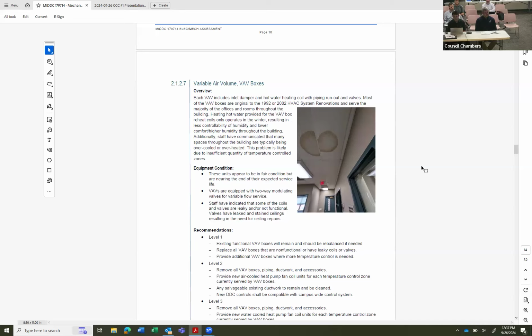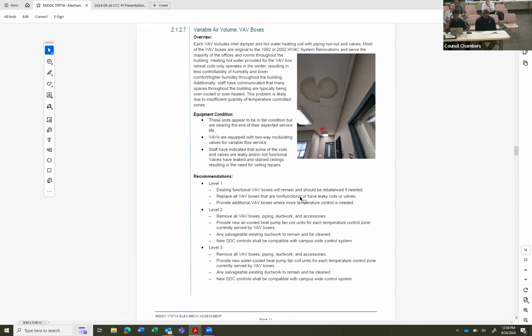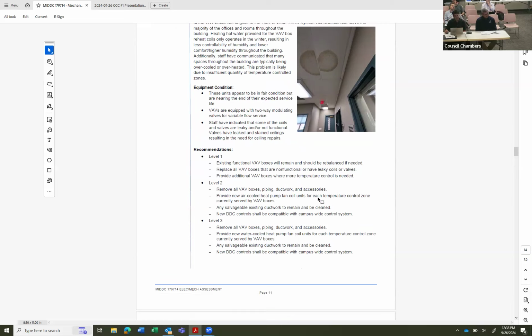And in general, these boxes, I didn't get to inspect many of them, but based on the condition of some of them that I did see and the installation plans that we have, they do appear to be in fair condition, but are nearing the end of their expected service life. It also has been noted that some of them are non-functional and some have leaky valves or coils, as you can see in the picture there. So any instances like that, we would certainly replace on a level 1 upgrade. But as a whole, the majority of them would stay the same.